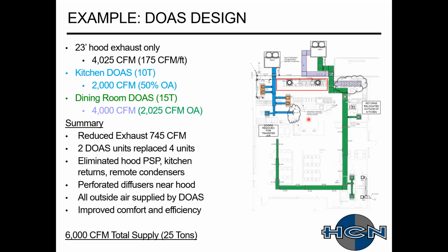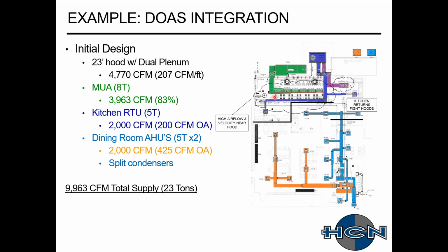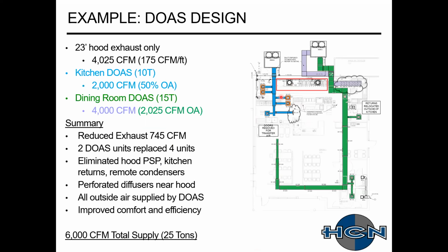Also opened up the kitchen a little bit here. Used some perforated supply plenums to bring in that makeup air. So it's nice laminar flow, using transfer air to its fullest here. So we're able to reduce the exhaust CFM from the previous design. Instead of having 4 units, we're going down to 2, eliminating that PSP. The previous design actually had the makeup air plenum in front, the dual plenum configuration. So we're reducing a lot of the ductwork, and giving you a little bit more tonnage, a little bit less CFM as well.